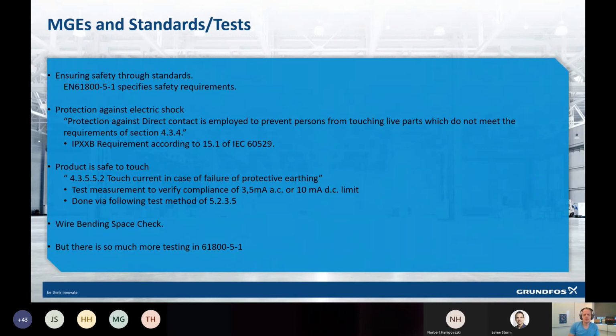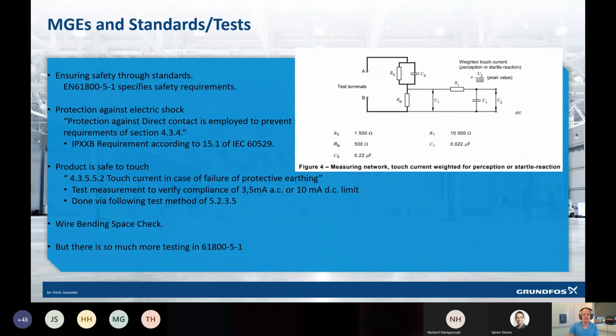We need to make sure our product is safe to handle, so I've also been handling touch current tests, which we measure using this circuit. It's specified in the standard that this measurement should be below the limit of 3.5 milliampere AC or 10 milliampere DC.